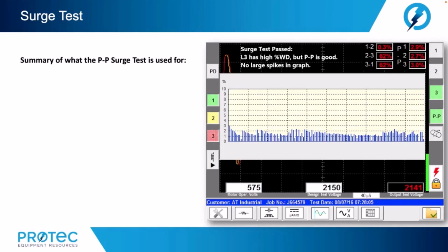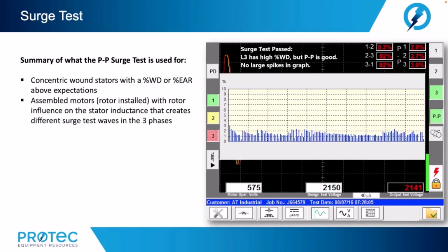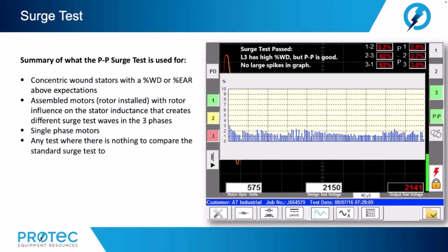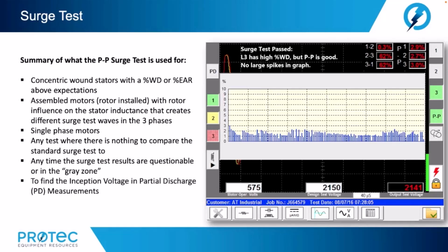So, summary of what the P2P surge test is used for. It is used for concentric wound stators with a %WD or %EAR above expectations. Assembled motors, the rotor installed, with rotor influence on the stator inductance that creates different surge test waves in the three phases. For single-phase motors, any test where there is nothing to compare the standard surge test to, and any time the surge test results are questionable or in the gray zone, or to find inception voltage in partial discharge measurements.